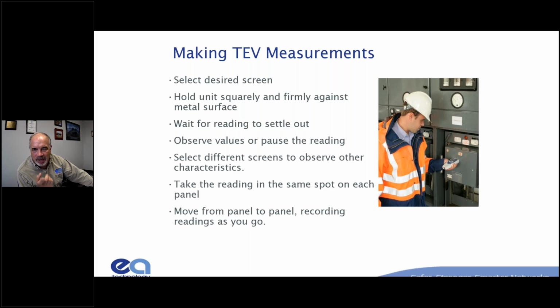You're holding the instrument tight against the outside of something where there's high voltage inside. So don't do it on the upper cabinet, which is all instrumentation and protection control. Hold it down on the breaker cabinet, or on the back, on the cable door, or on the vault of the transformer, or on the tank of an instrument transformer. That's where you're trying to see if something's going on inside. It takes a few seconds to settle out, and then you can record the data, review the data, depending on what information you need.